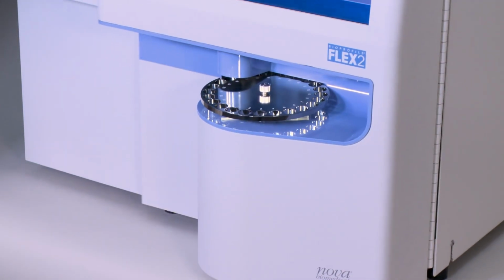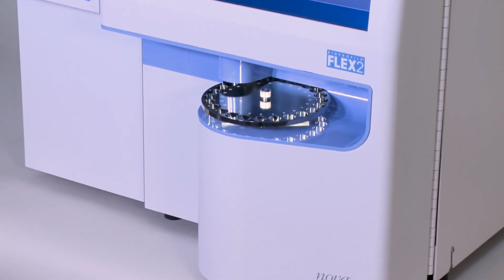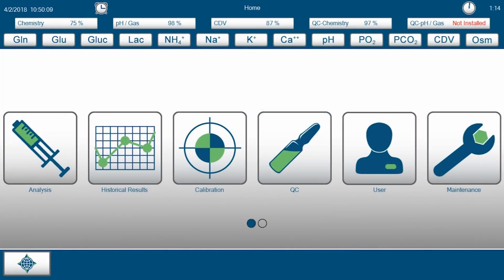If anything has changed, let's say a new reagent cartridge has been installed, the system will automatically populate the new RFID information and prime the new reagents. This smart maintenance will begin every time the analyzer door is closed, and a countdown timer icon will appear in the top right-hand corner of the user interface.